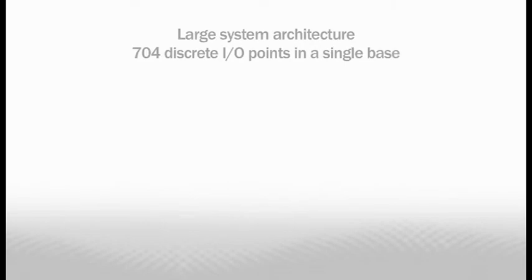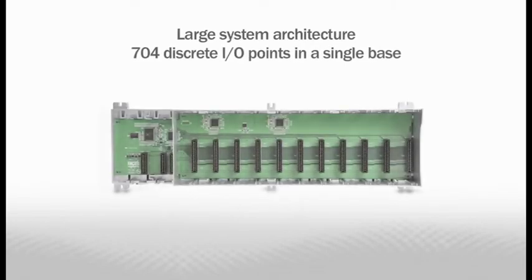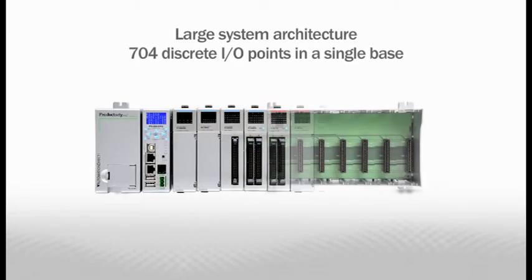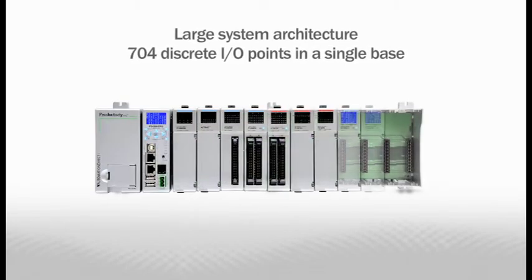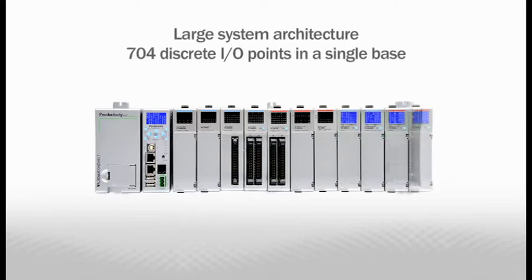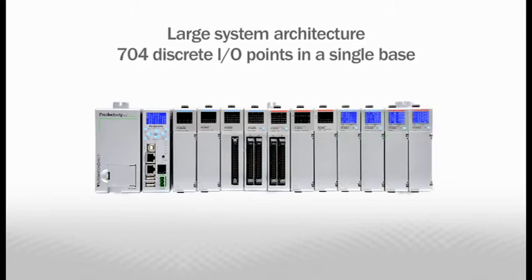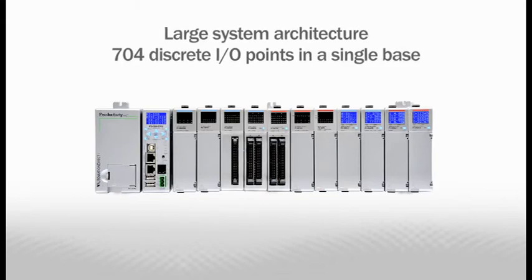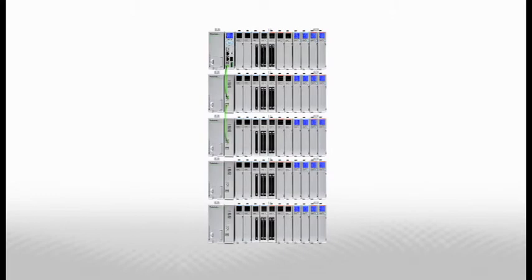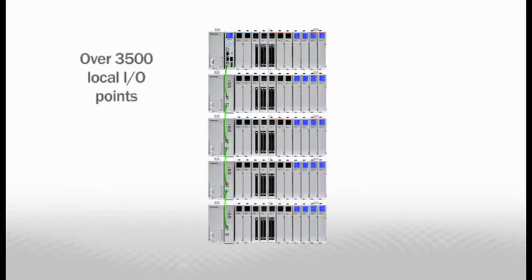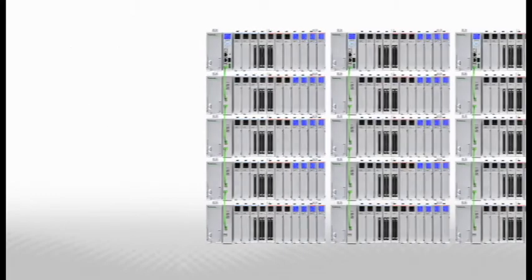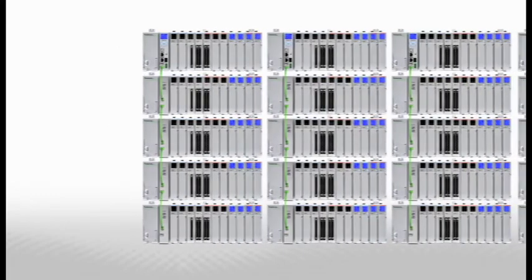The Productivity 3000 is capable of handling large system designs. Using the 11-slot base and our 64-point discrete I.O. modules, you could have 704 discrete I.O. points in a single base. Local expansion I.O. allows for 5 racks in a local system. That's over 3,500 local discrete I.O. points.